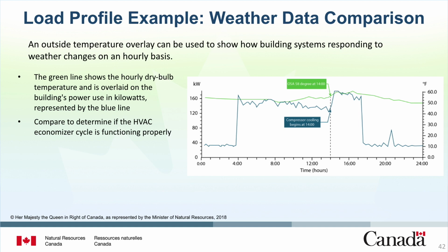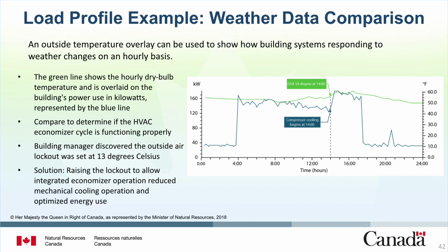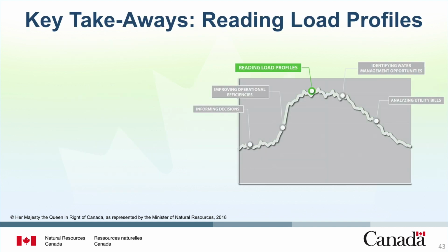In this example, a jump of about 40 kilowatts at 2 p.m. corresponded to the cooling compressor coming on. Based on this information, the building manager examined the economizer control settings and discovered the outside air lockout was set at 13 degrees Celsius. Raising the lockout to allow integrated economizer operation instantly reduced mechanical cooling operation and optimized energy use.